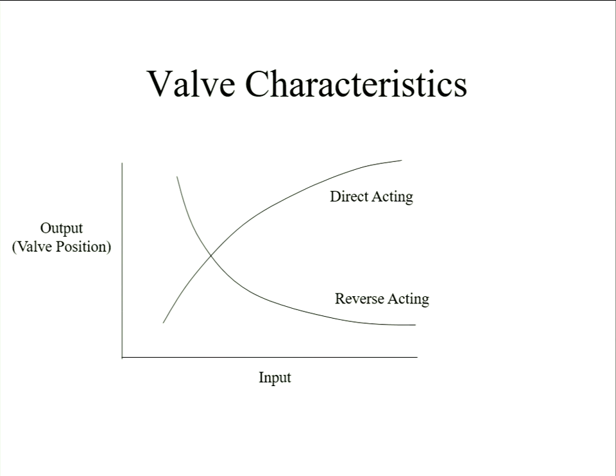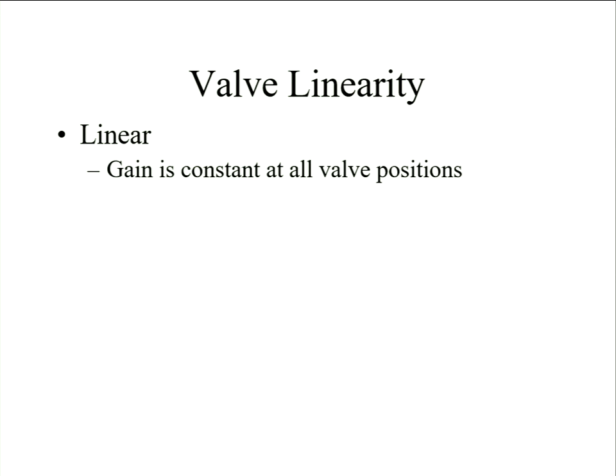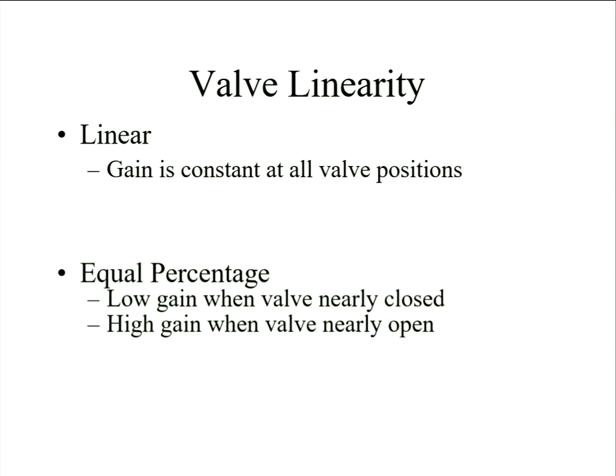Now, if we go back to Ziegler-Nichols, that was a lot based on process gain. So if I do a test with the valve here, I've got a different process gain to when I do it here. So there are some strategies that can be adopted in the controller. So you might do some gain scheduling, for example. So when my valve is 20%, I'll apply one gain value. When my valve is 80%, I'll apply a different gain value.